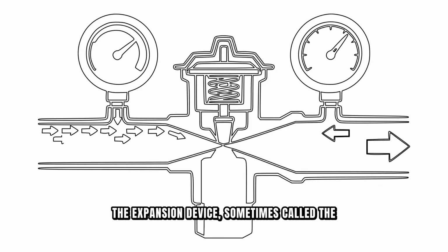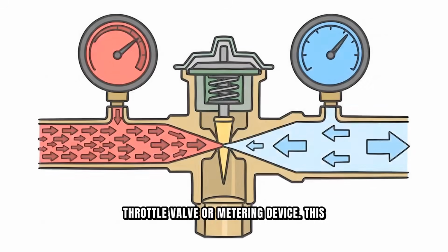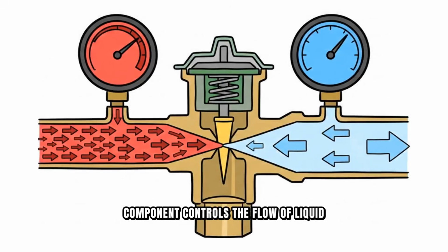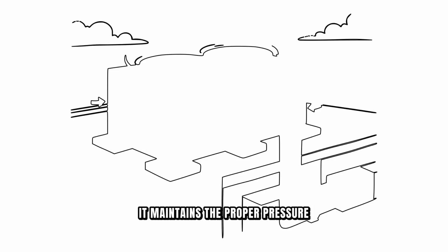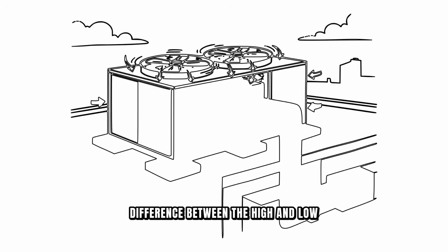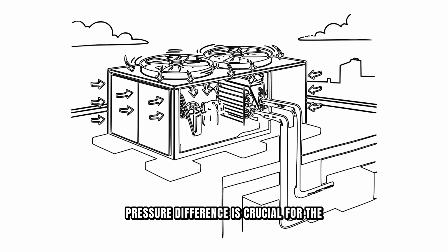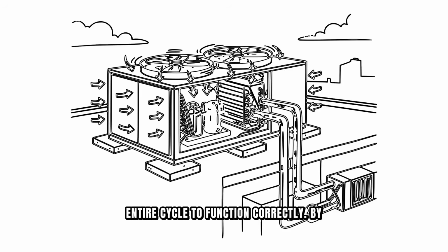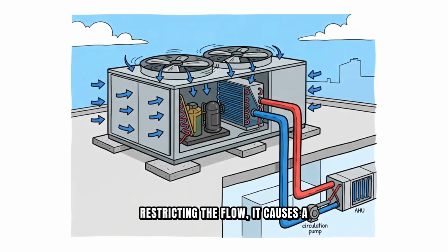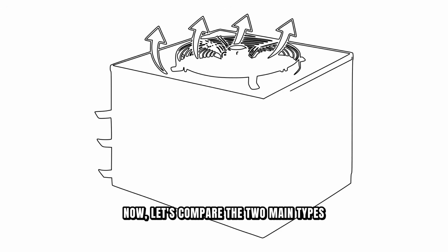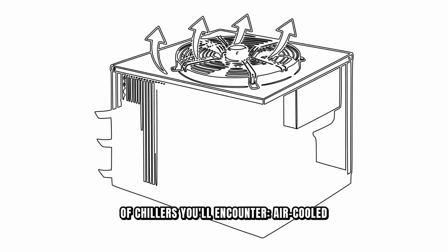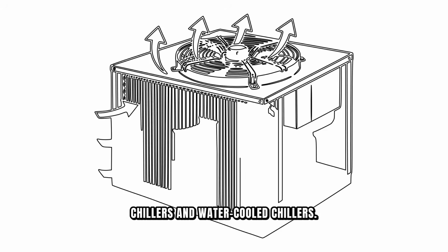The fourth component is the expansion device, sometimes called the throttle valve or metering device. This component controls the flow of liquid refrigerant from the condenser into the evaporator. It maintains the proper pressure difference between the high and low pressure sides of the system, and this pressure difference is crucial for the entire cycle to function correctly. By restricting the flow, it causes a significant pressure and temperature drop in the refrigerant. Now let's compare the two main types of chillers you'll encounter: air-cooled chillers and water-cooled chillers.